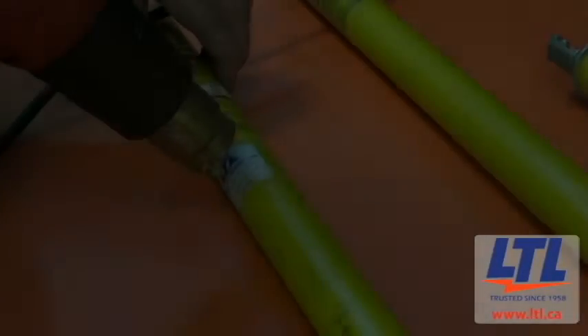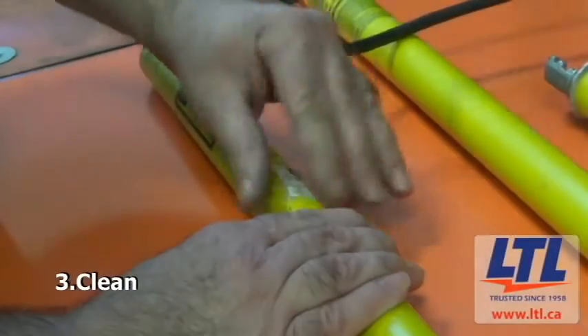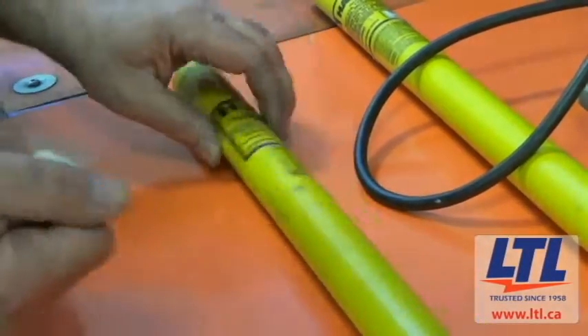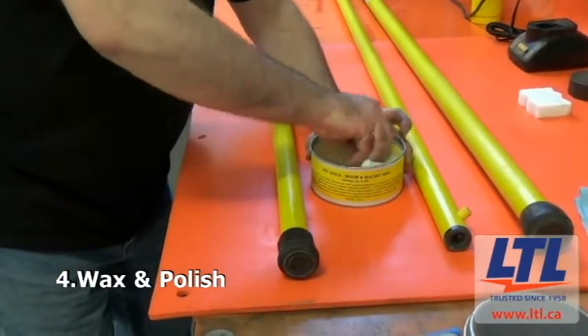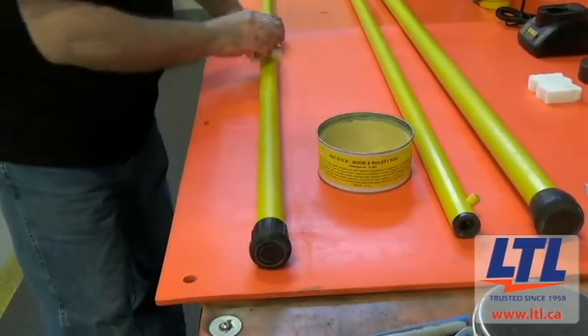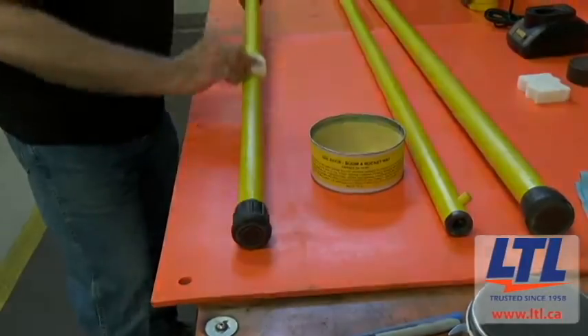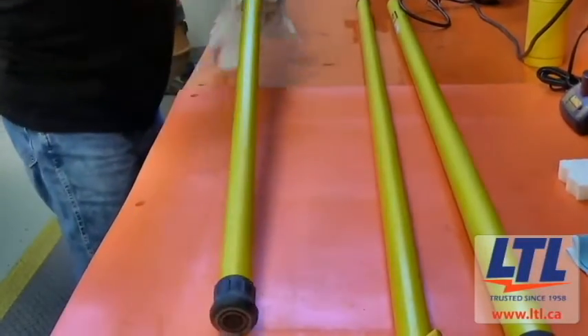The technician will remove any existing labels and clean any dirt, oil, and contaminants off the tool with a soft cloth and alcohol. Then, using a specialty LiveLine tool wax, the entire tool is waxed and polished. All surfaces are waxed using a hot stick wax. The technician ensures the wax is dry so the tool is properly protected when going through testing.